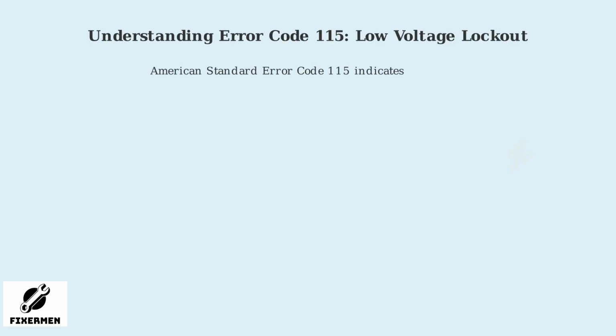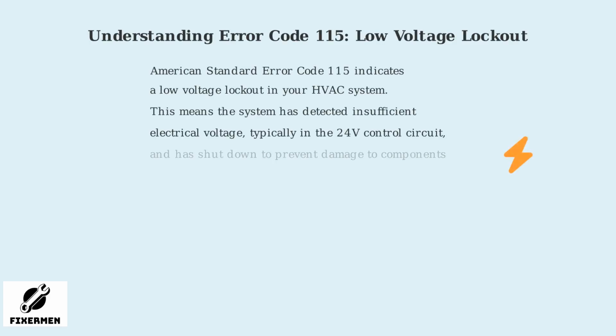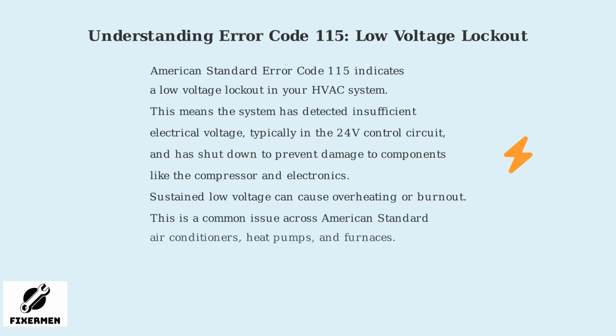American Standard Error Code 115 indicates a low voltage lockout in your HVAC system. This means the system has detected insufficient electrical voltage, typically in the 24 volts control circuit, and has shut down to prevent damage to components like the compressor and electronics. Sustained low voltage can cause overheating or burnout. This is a common issue across American Standard air conditioners, heat pumps, and furnaces.